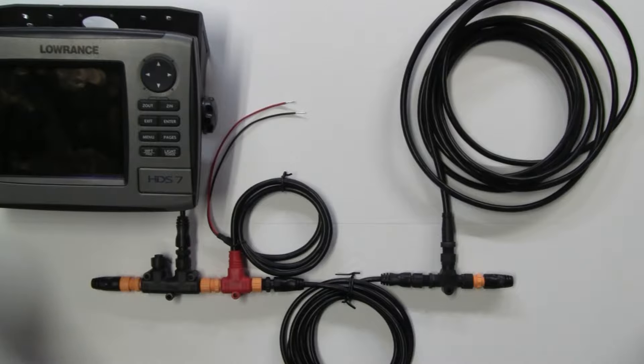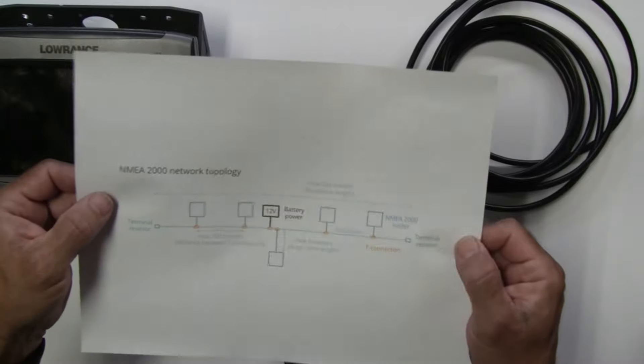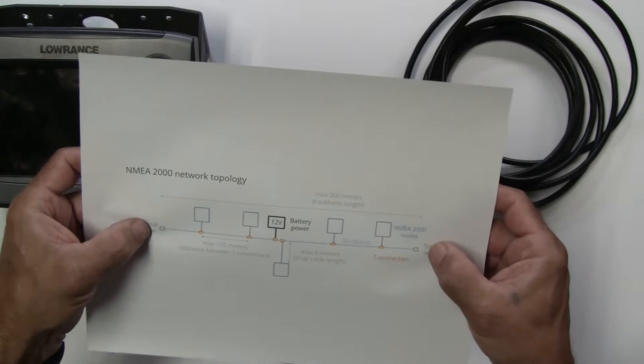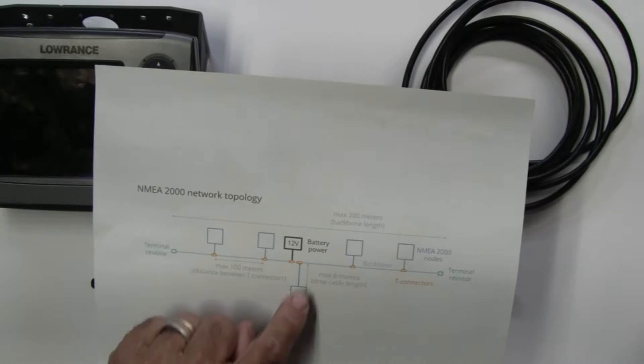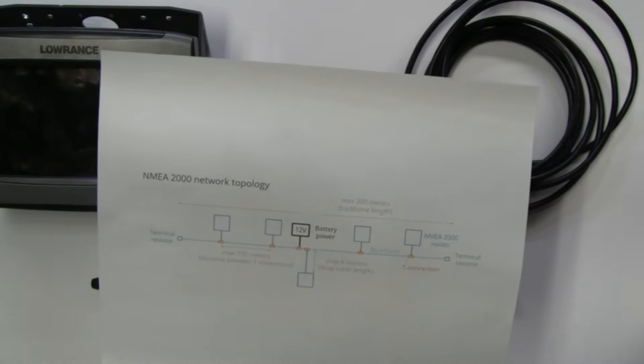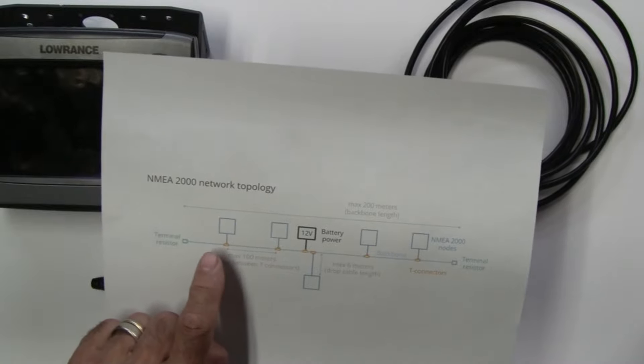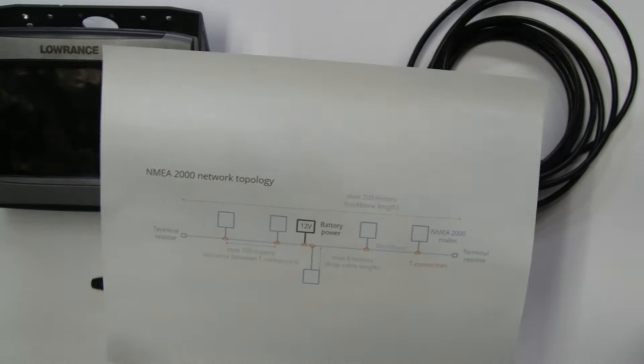Let me show you a diagram of what an NMEA network might look like and the lengths that are involved. So you can see the overall length is 200 meters for the backbone, that's end to end from terminal resistor to terminal resistor. The drop cables to the devices or nodes as they're called is a maximum of six meters, which is fairly significant. And then the max distance between T connectors is going to be 100 meters.